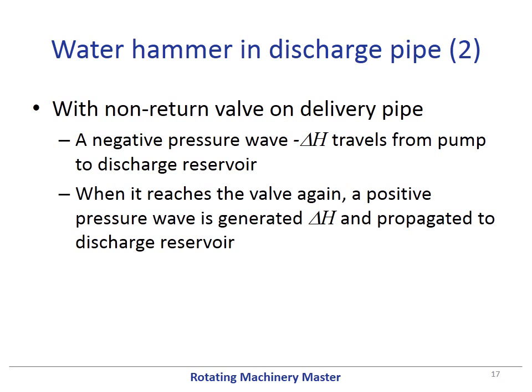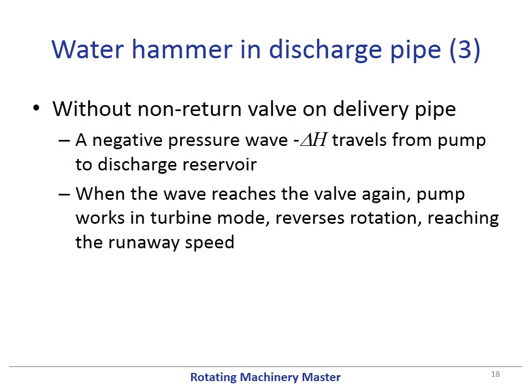The previous slides show the behavior of water hammer with a non-return valve on the delivery pipe. If there is not a non-return valve on the delivery pipe, when the wave reaches the valve again, the pump works in turbine mode, reversing rotation and reaching the runaway speed.